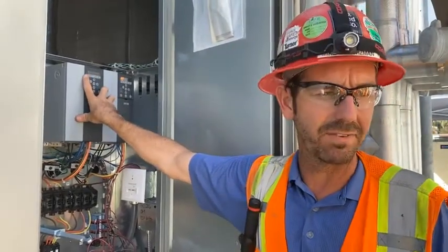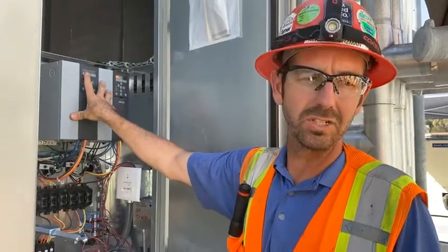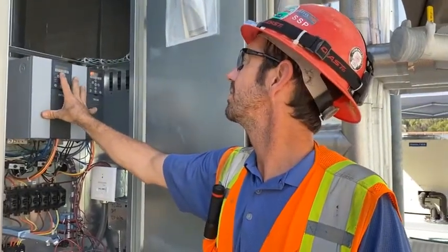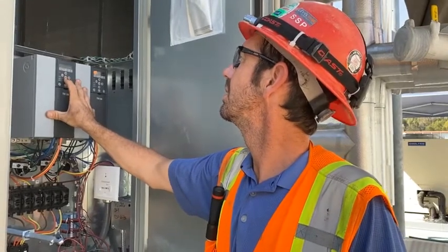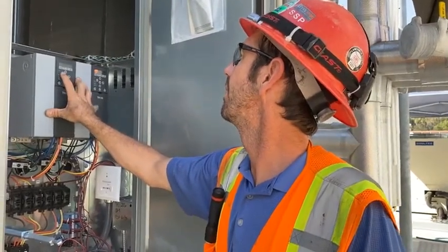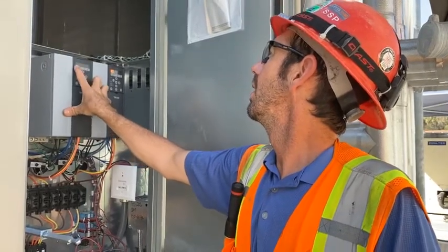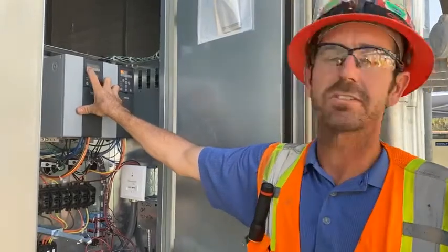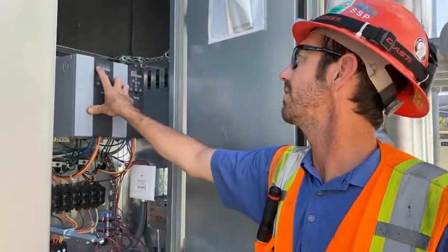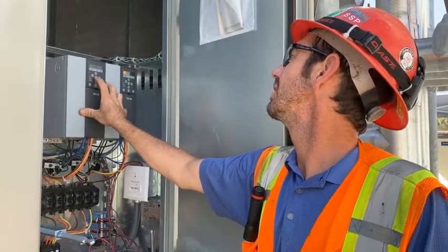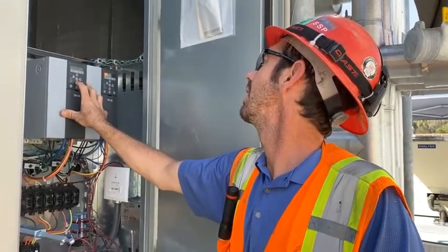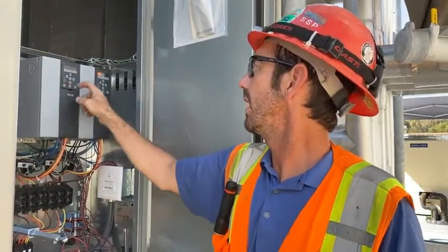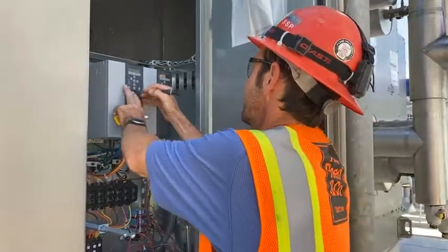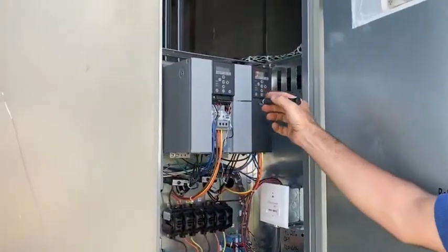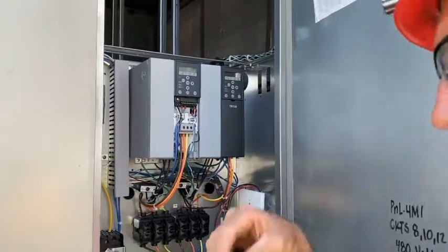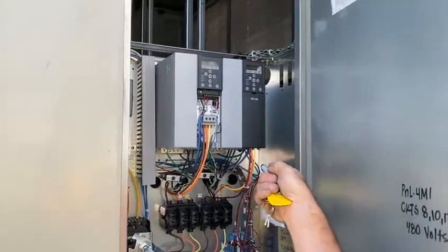Analog input we have set up for a 0 to 10 volt signal. We're not using any digital inputs into the drive. Actually we are. 5-10 is terminal 18. That's your start. So the BMS guys are using that digital input for start. And then 5-12 is a terminal inside here, on this terminal board here. So 27 is going to be the third from the left. So this input right here, 18, is going to be your start.